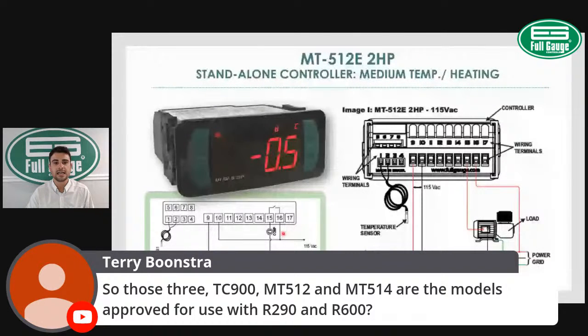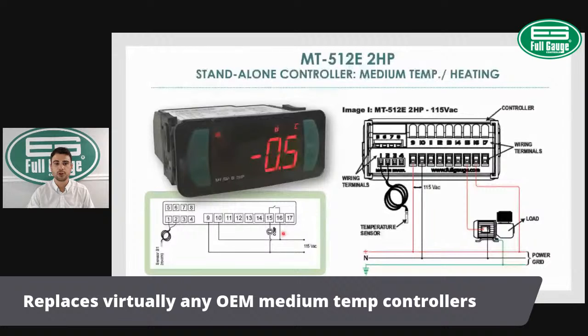So those three, TC900, MT512, and MT514, are the models approved for use with R290 and R600? The answer is yes, Terry. They are approved for R290 and R600. In fact, we actually worked with UL to ensure that those controllers are not a source of ignition, and they can be used in any flammable refrigerant application. So yes, in addition to those three models, the MT444 is also certified for flammable refrigerant application. Thanks for your question, Terry.